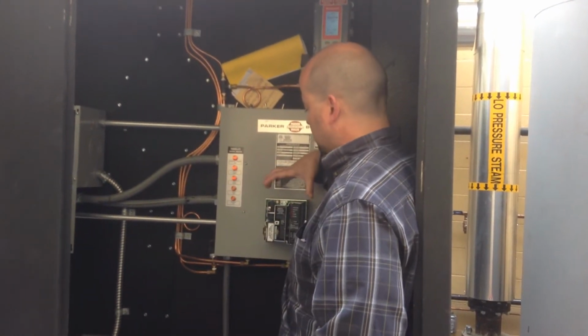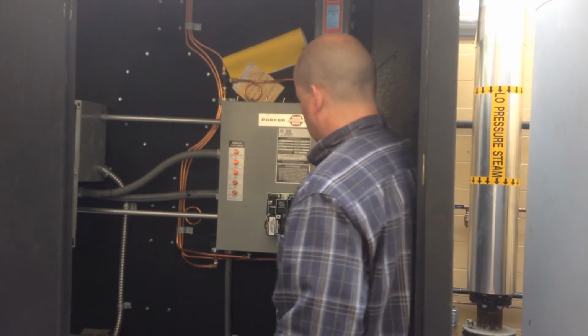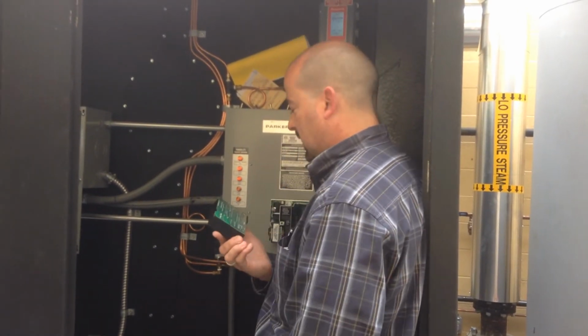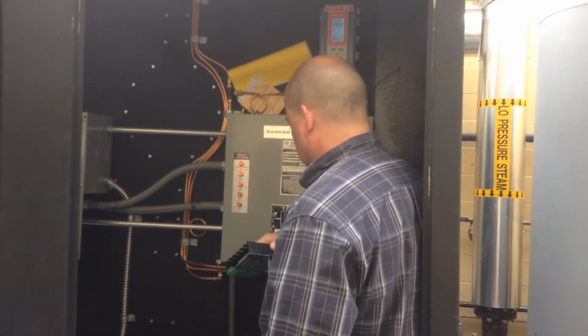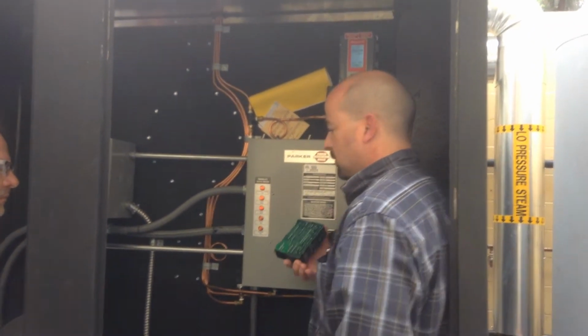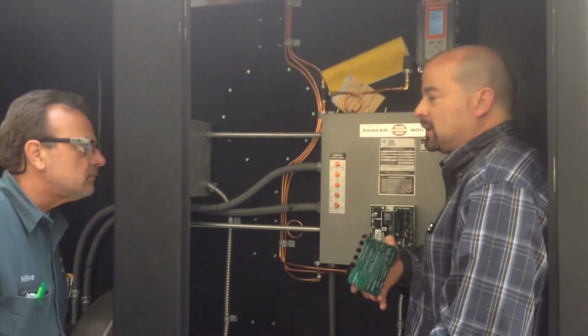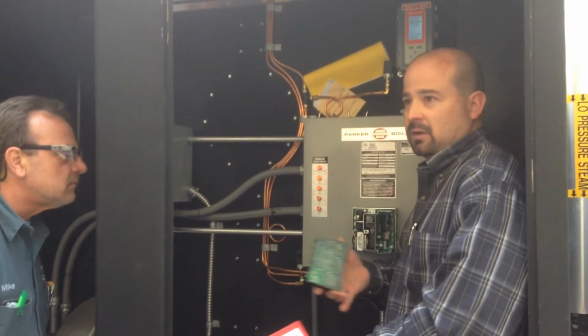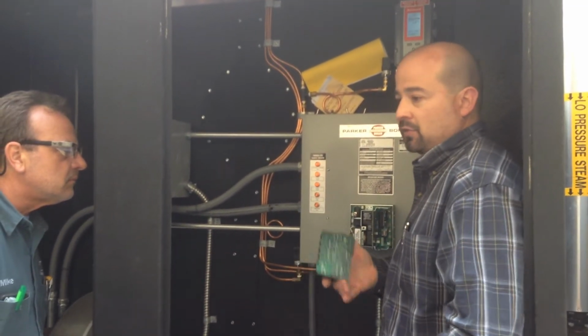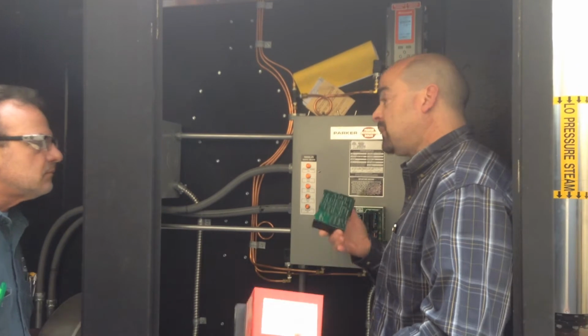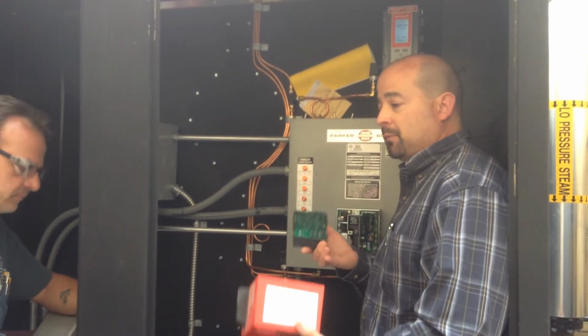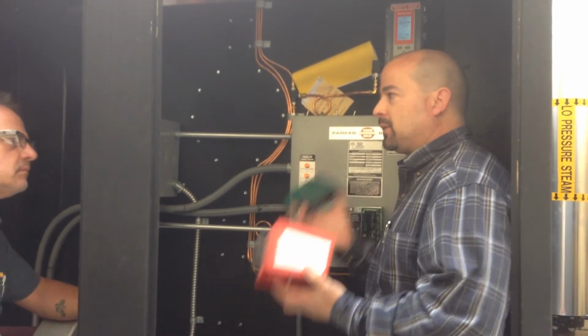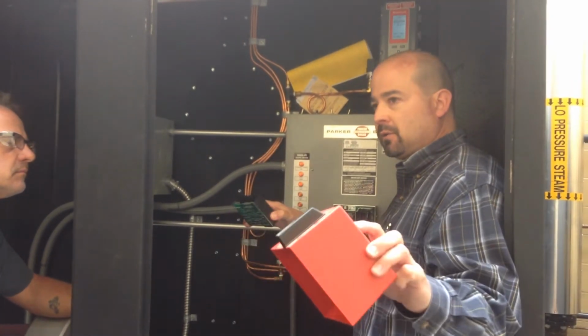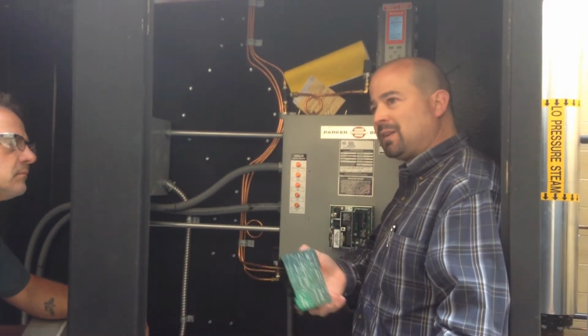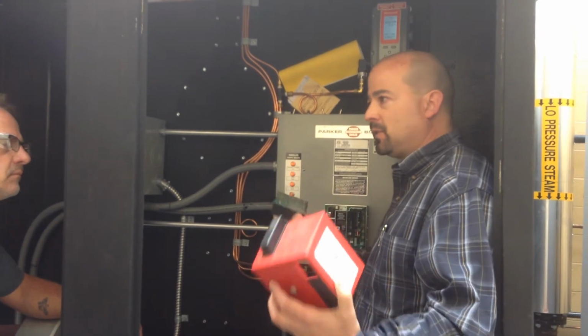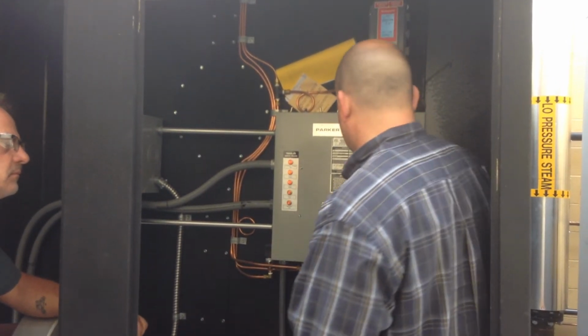This is modular too, so you have the program module, which is this device here that pulls out, you have the amplifier that pulls out, and then you have the chassis. So if you think you're having a problem with this, let's say when the warranty's up, because for 1 year everything, parts and labor, is included, so just call us if it's within a year. After a year, if you're having problems, don't just go buy a new control, bring us the control. We have a counter, we plug the control into a simulator and we test it, so you don't have to spend $500 if you don't need the control. We'll tell you if it's wrong or if it's bad.